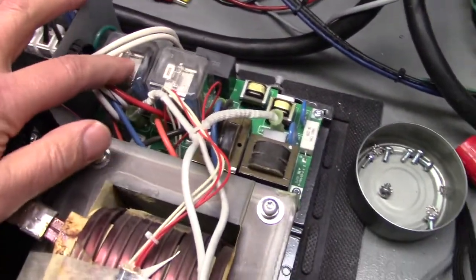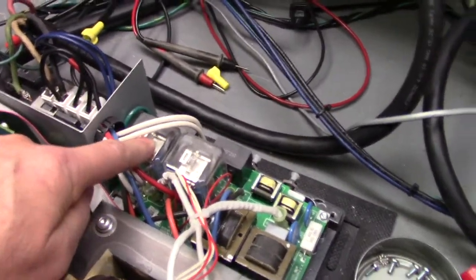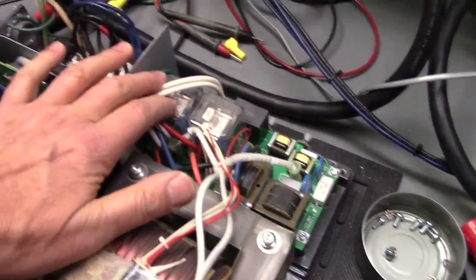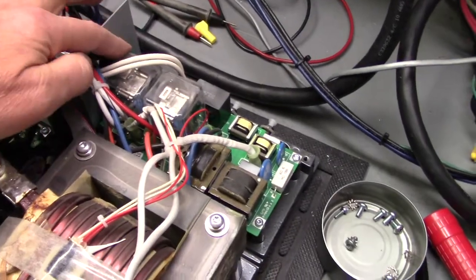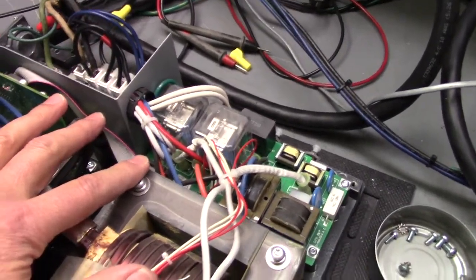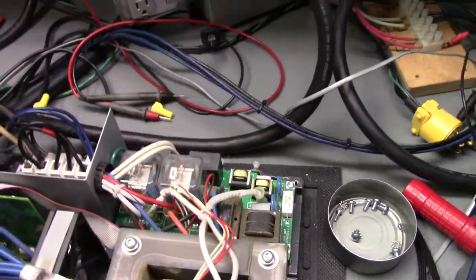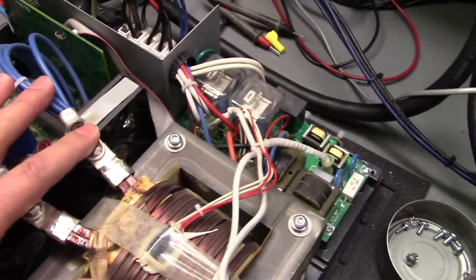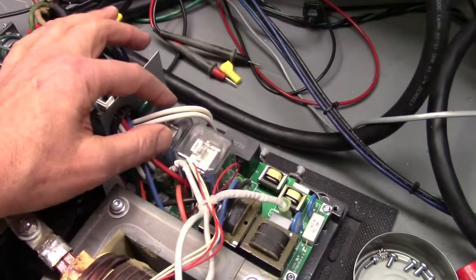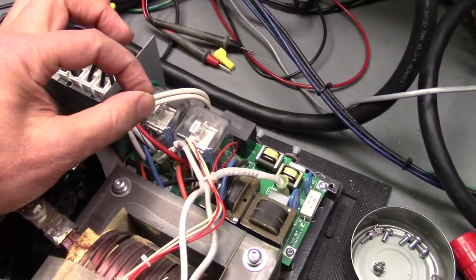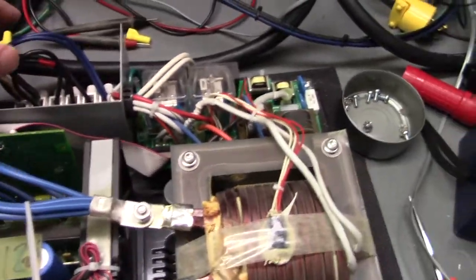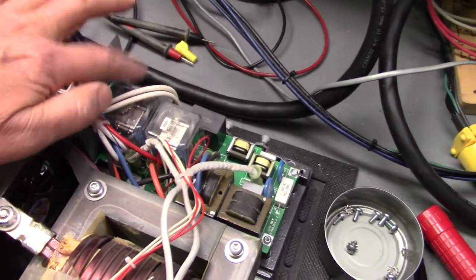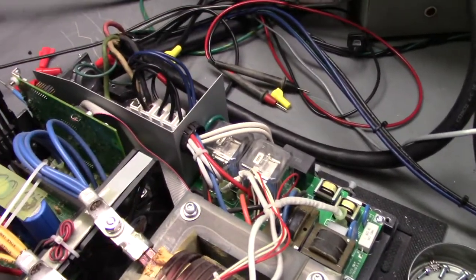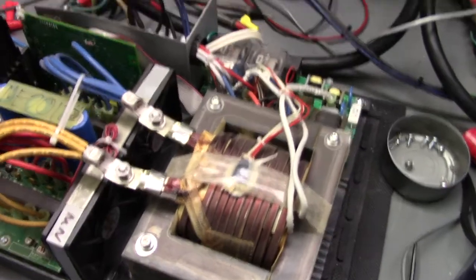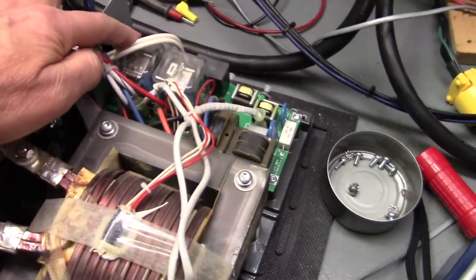The ground bond relay, what that does is, the code is that you're supposed to bond the neutral to ground at the source of power. So when the inverter's running, this is the source of power, and this relay will actually drop out and connect your ground to your neutral, so it's bonded at this point. When you have AC coming in, this relay will open up, releasing that bond, and then your bond is back at your power panel or generator, wherever the power is coming from. So that's your AC bond relay.